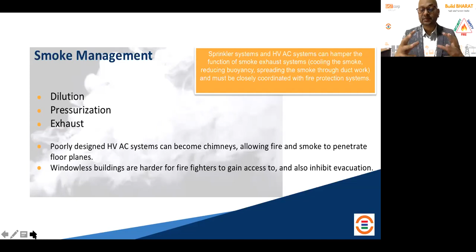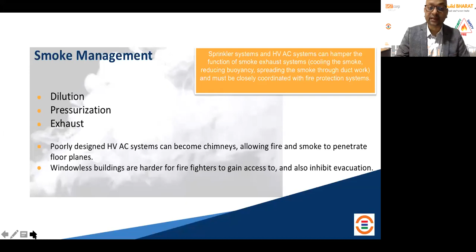Are you expecting ventilation to come after sprinkler? That may not be the right idea. Your building system integration should have the sequence in place, and automation also should have a sequence, so that they don't affect or overlap with each other. That's a very important parameter, and mostly engineers, because they don't have that responsibility on the contract or access to the other parts of the building engineering, this point gets eliminated or doesn't get captured during actual construction or commissioning stage. But it's very important how much sequence is going to be there. Even detection, sprinkler, and ventilation all three have to be coordinated in sequence, because only then will it have correct implementation and effectiveness for your smoke management.